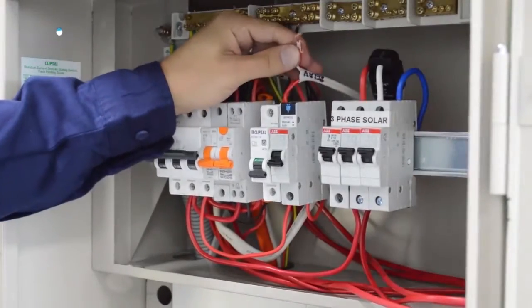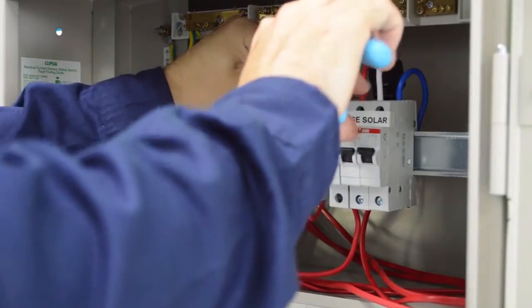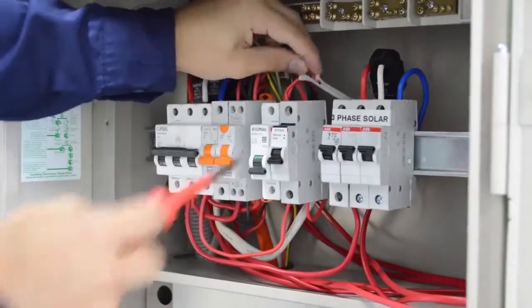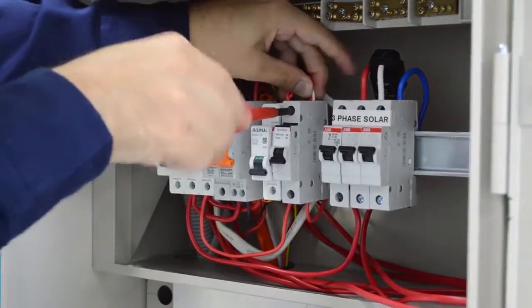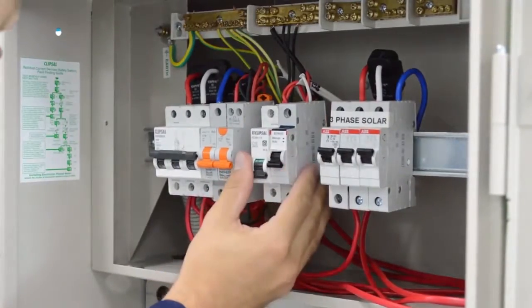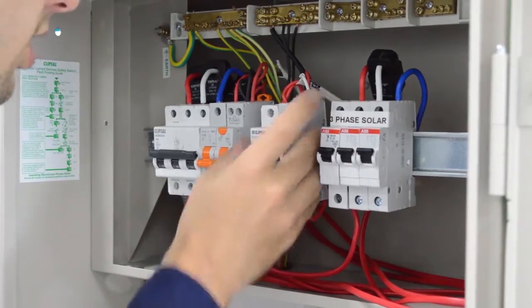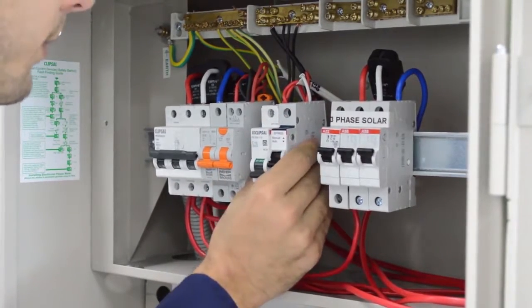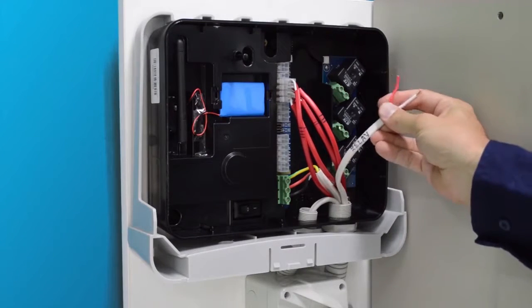You can now connect the white from the twin active, the load together, and connect them into the top of the bypass switch. As you can see, this bypass switch is installed in parallel to the carbonTRACK relay. This is very important. Now I'll demonstrate switching with a circuit breaker internal bypass switch.